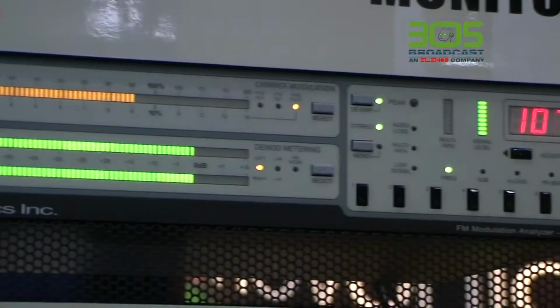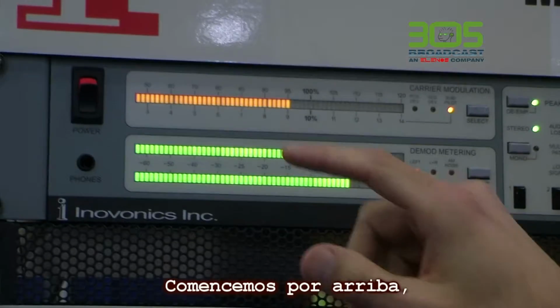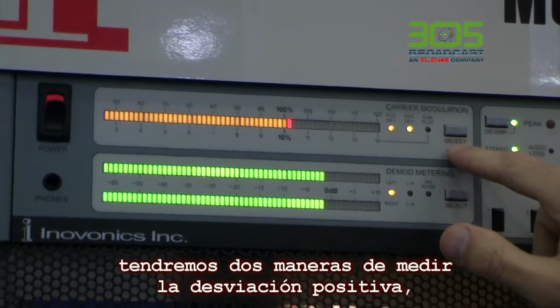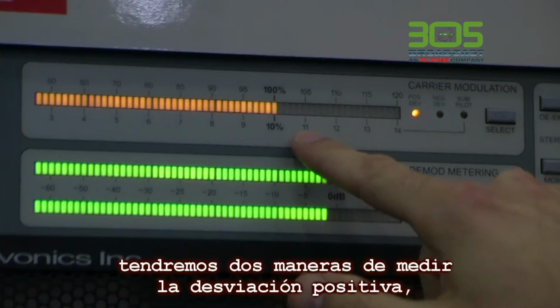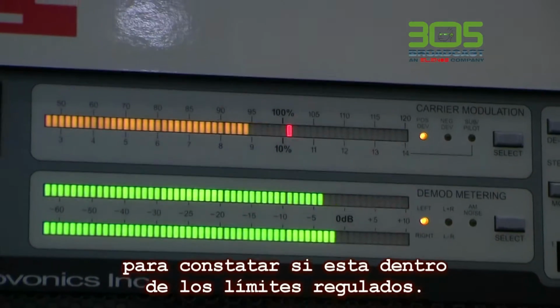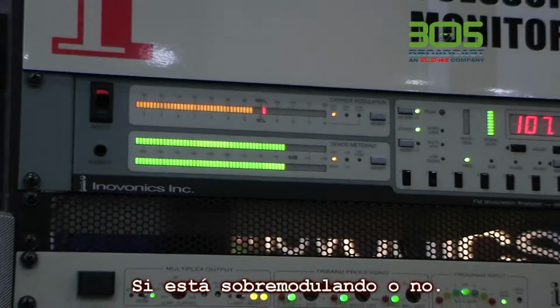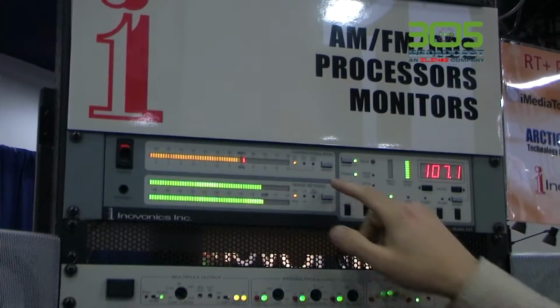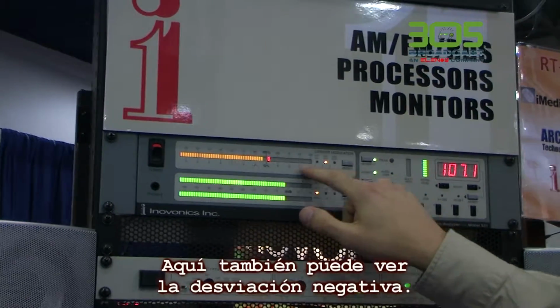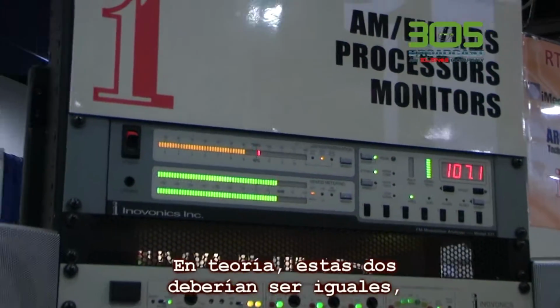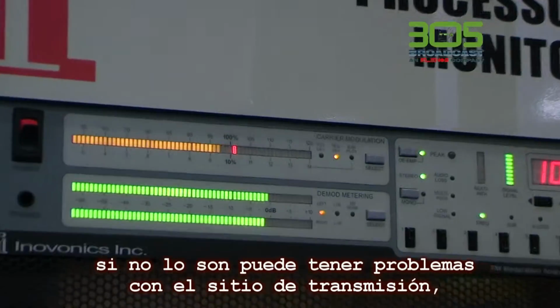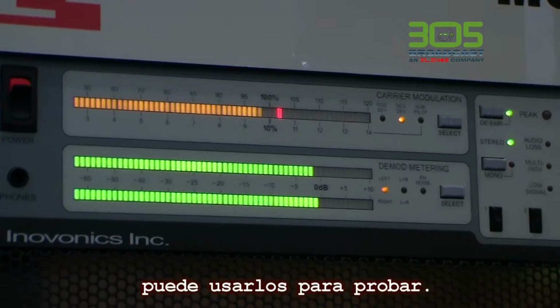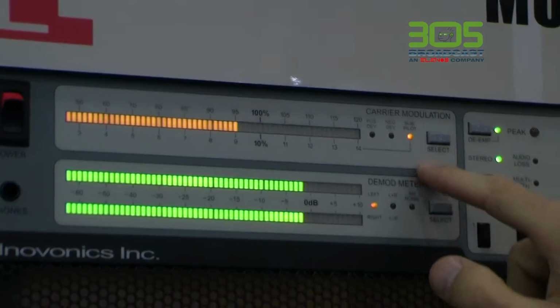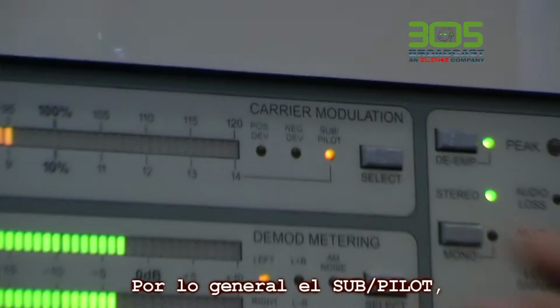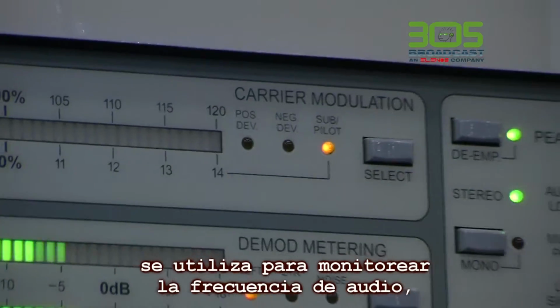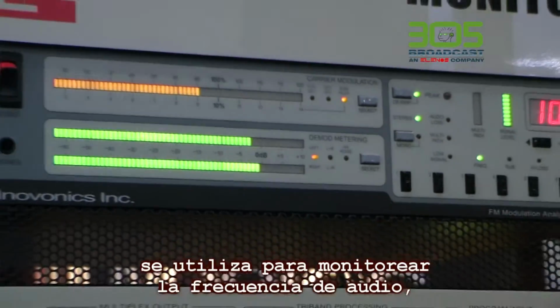If we start up at the top here, we've got ways to measure positive deviation, so to see if you're within government regulations or if you're over-modulating or not. You can also check negative deviation. Ideally, those two should be the same. If they're not, you might have an issue at the transmitter site, and you can use that to test that. The sub or pilot is usually used to monitor RDS frequency or something like that, and I can show you that in a little bit.